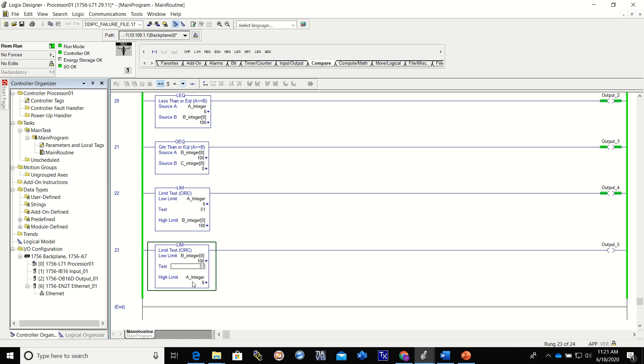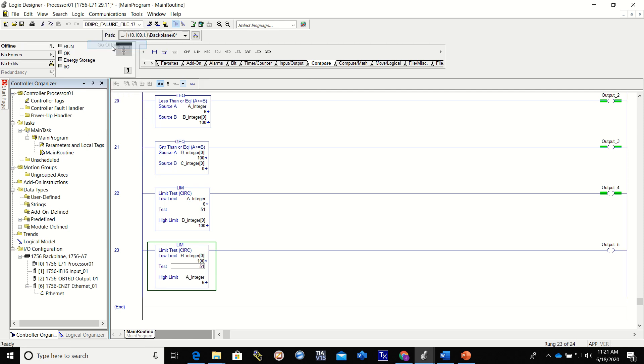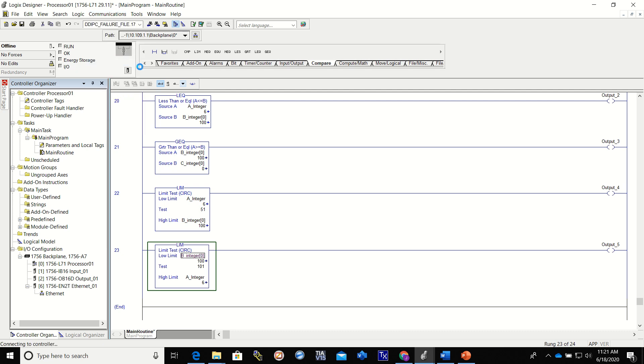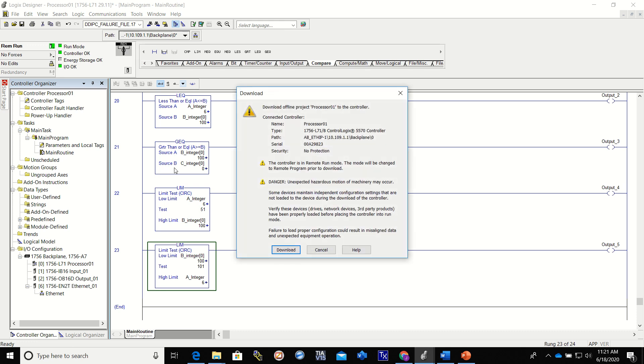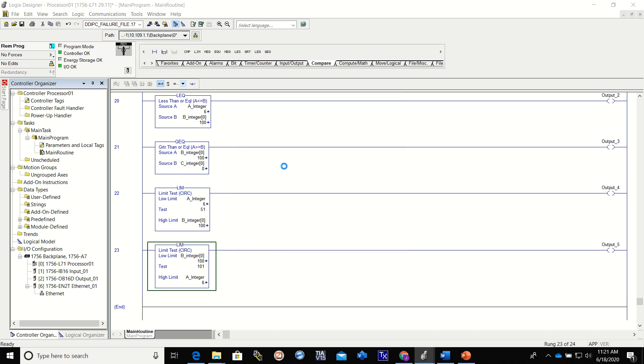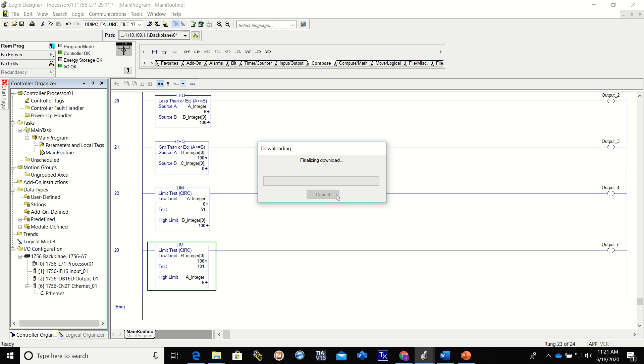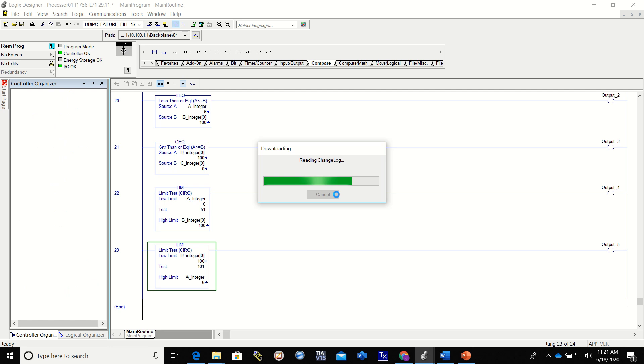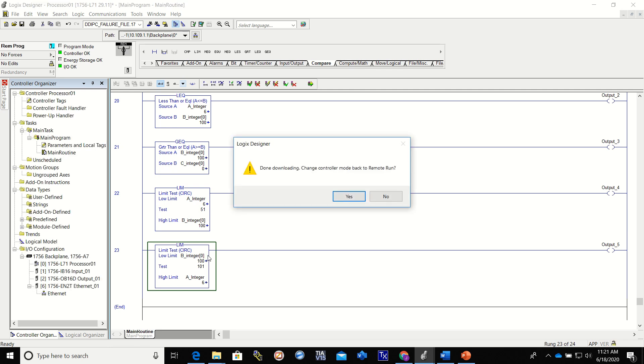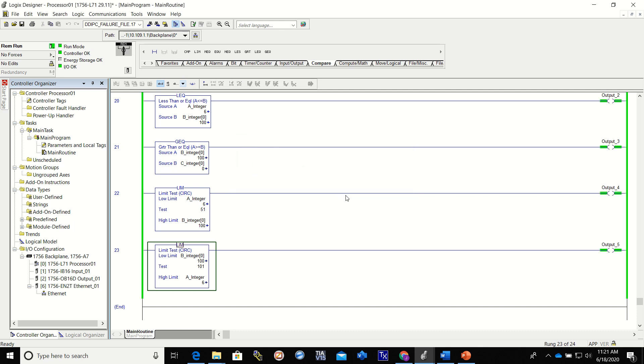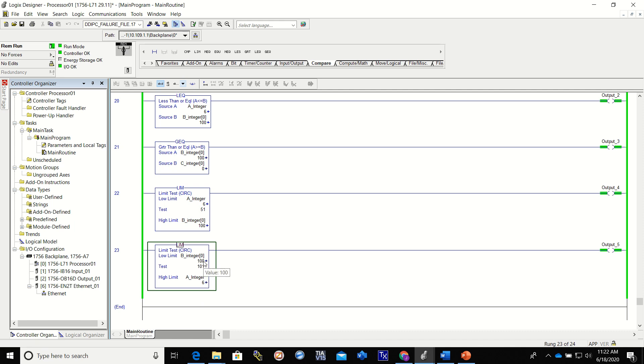Okay, so you see that right there. I'm going to go ahead and I'm going to go offline and I'm going to just change this value on my test to 101, and I need to re-download that. Now this output 5 will come on as soon as I hit yes. See it came on, because again our low limit is higher than our high limit value, so it's looking for values outside of that range, so anywhere from 5 on down or 101 on up to give us a true.